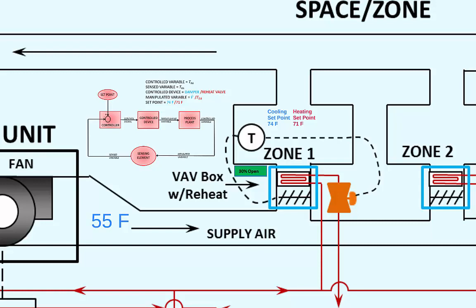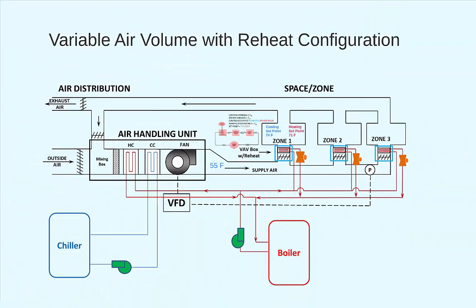Remember how we said maintaining a minimum setting on the VAV box airflow can create an issue of overcooling for the space if the cooling requirements were quite low? Well, providing this reheat capability helps curb some of those comfort complaints that would occur from overcooling the space. So the explanation we just provided is how a VAV with reheat system configuration should be controlled. However, there are some inherent issues here.